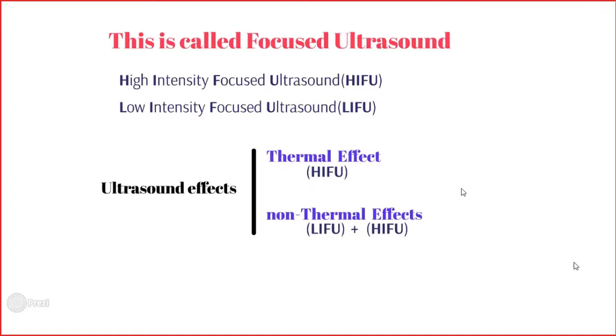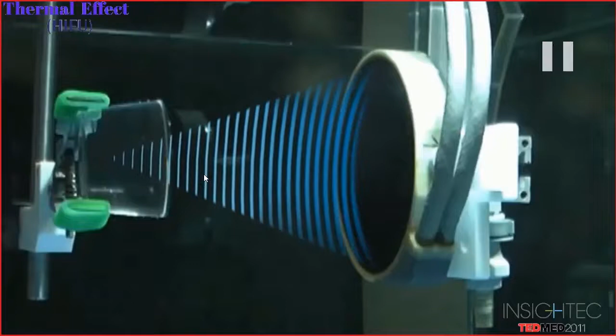So here you can see this is a testing chamber which is filled with water, and on the right hand side you can see a HIFU probe, which is a spherical probe of piezoelectric elements and modules. And on the left hand side, you can see that there is a tissue phantom. If we turn on the electricity and give it to the piezoelectric elements, then this spherical shape is going to make the ultrasound waves and the sound waves be gathered and focused in the tiny region of our interest. And as you can see here in the picture, it is going to degenerate or ablate this part of the tissue phantom and makes an elliptical-like focal region.